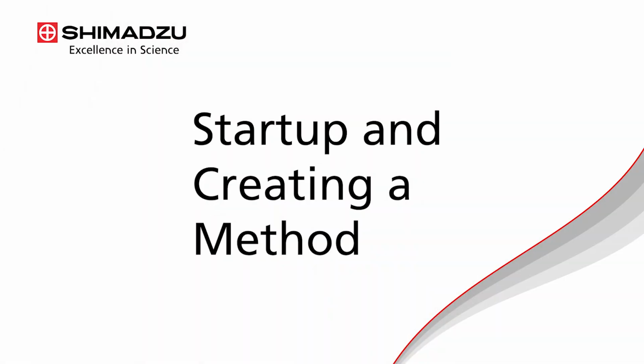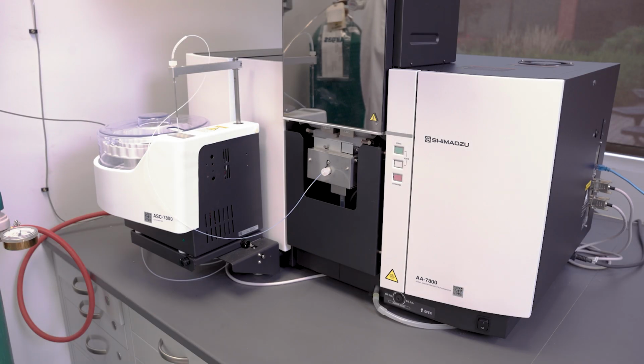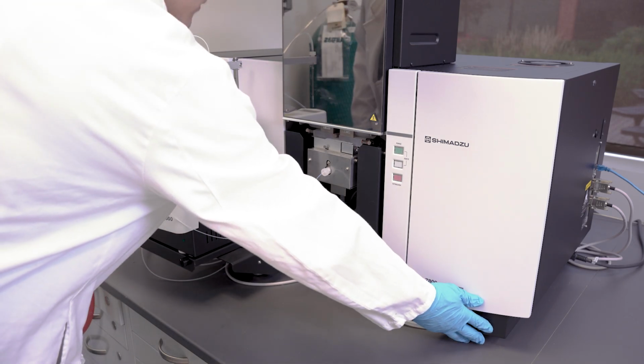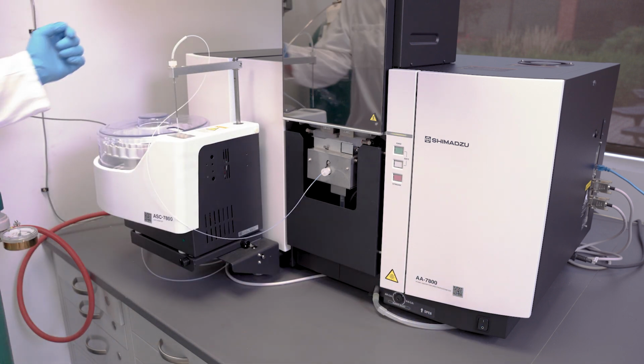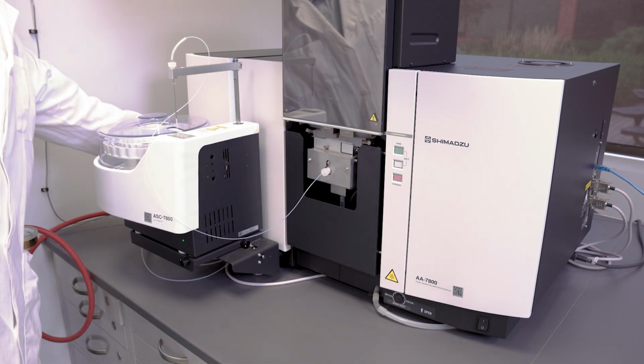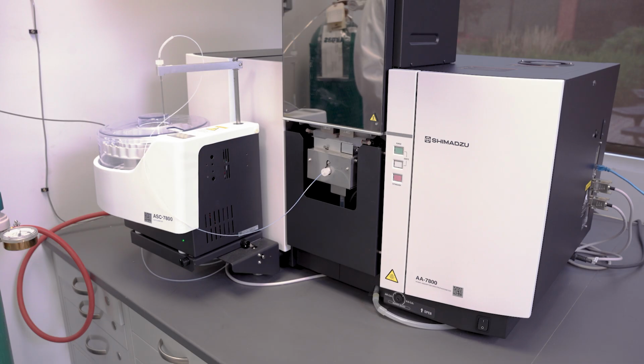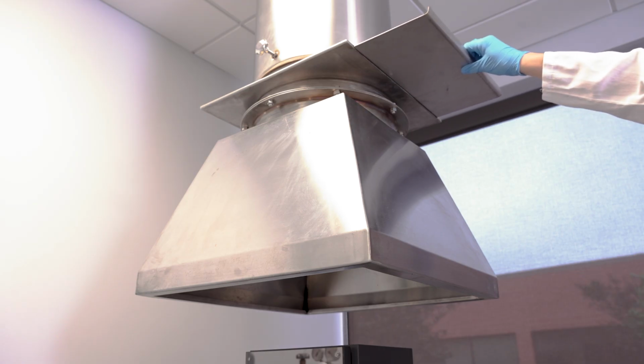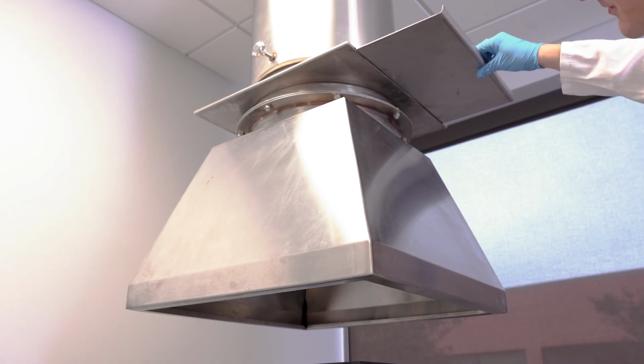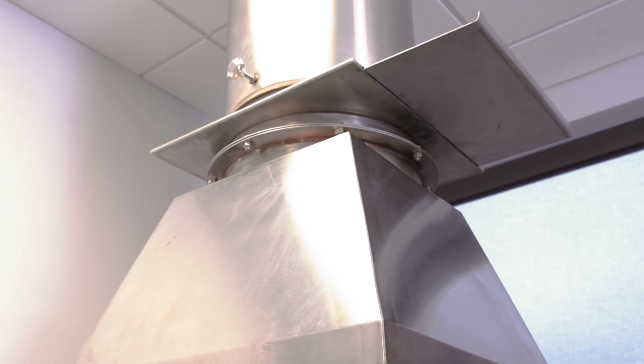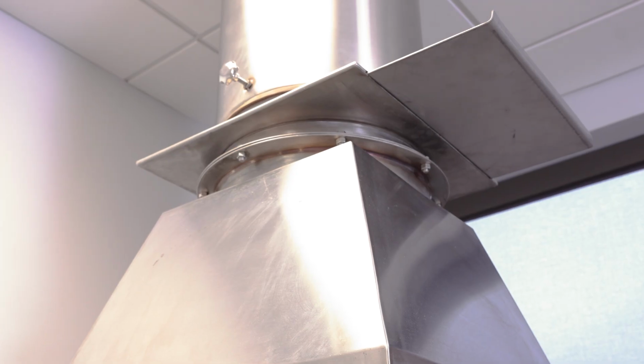To turn the instrument on, flip the power switch on the bottom right-hand corner of the instrument to on. If you have the auto sampler, also flip its switch to on. Note that if you have the GFA on your AA-7800, the auto sampler controller mounts inside the GFA. Otherwise, it will be sitting on a stand to the side of the instrument. Make sure to open the ventilation that you are using for your instrument. In this setup, we use an exhaust hood.